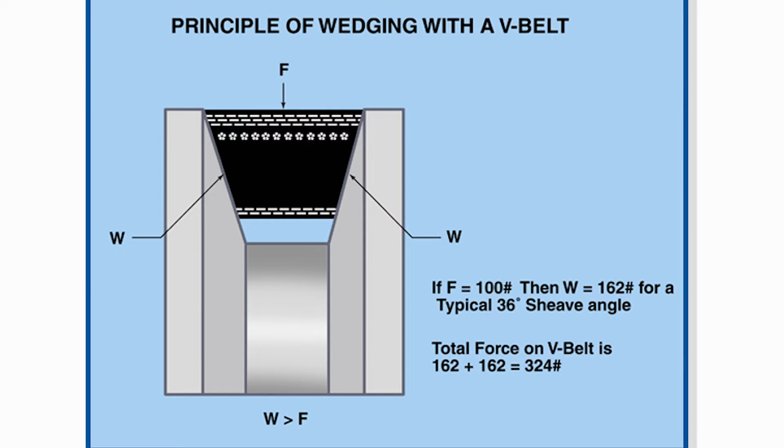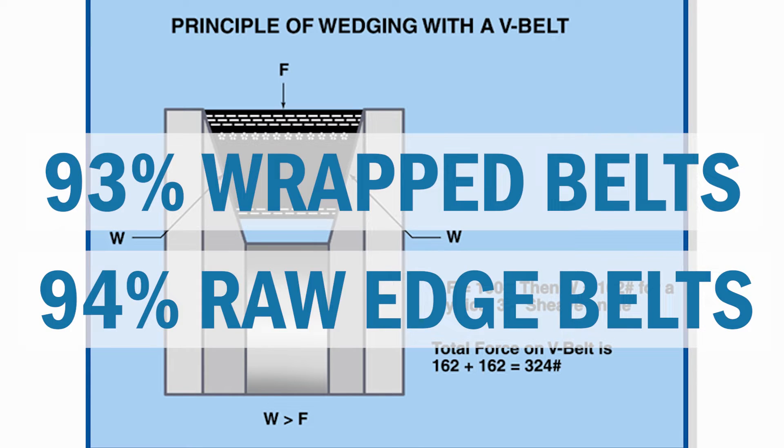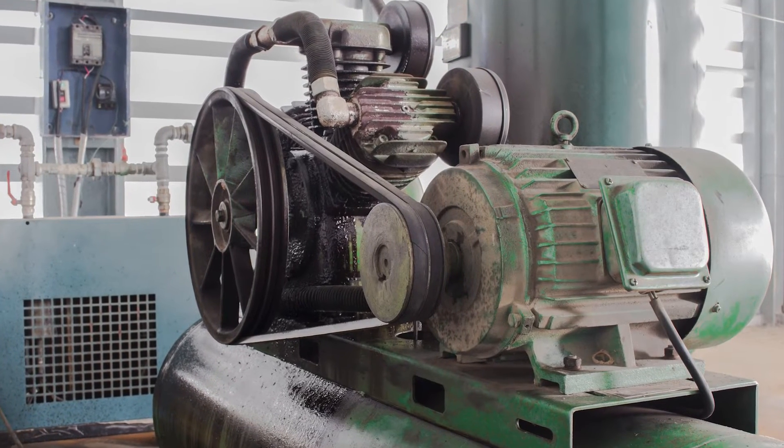Belts work on the wedge principle. There is a sheave, or pulley as some people call it, on the end of that motor shaft. As the motor shaft turns, it pulls the V-belt into that sheave and wedges it between the flanges of that sheave, and that creates the torque. Normal efficiencies are 93% for wrap belts and 94% for raw edge belts, because there is some slippage in the system. Belts must be properly tensioned to perform at this level.